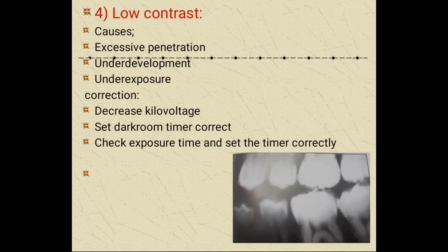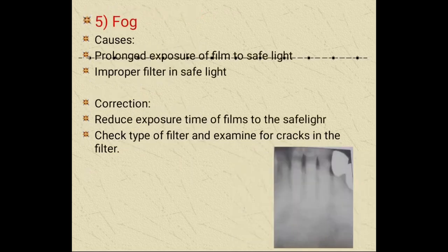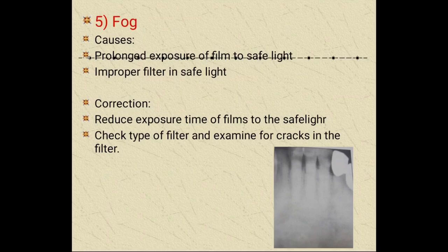Low contrast shows very low contrast, also not giving any details. Causes are excessive penetration, under-development, under-exposure. Correct by decreasing kilovoltage, setting the darkroom timer correctly, and checking and setting the exposure time correctly. Fogging of the film shows a fog-like appearance. Causes include prolonged exposure of film to safe light and improper filter in the safe light. We can correct it by reducing the exposure time of films to the safe light, and checking the type of filter and examining for cracks in the filter.